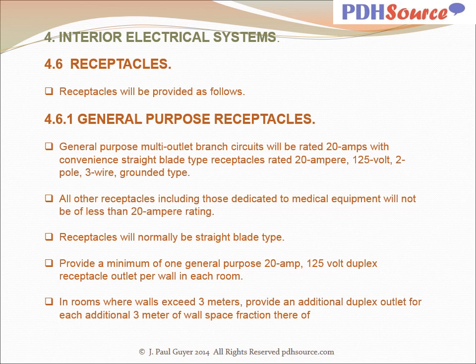Receptacles will be provided as follows. First, general purpose receptacles. General purpose multi-outlet branch circuits will be rated 20 amps with convenience straight blade type receptacles rated 20 amp 125 volt two pole three wire grounded type. All other receptacles, including those dedicated to medical equipment, will not be of less than 20 amp rating. Receptacles will normally be straight blade type.